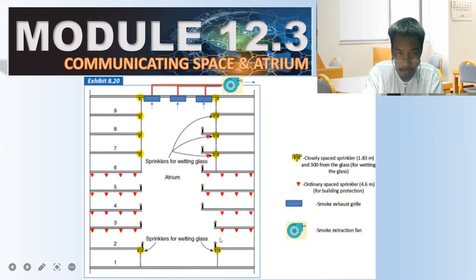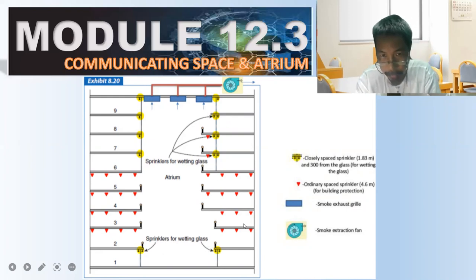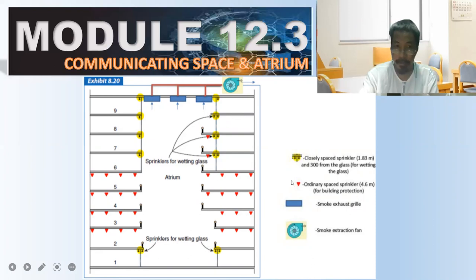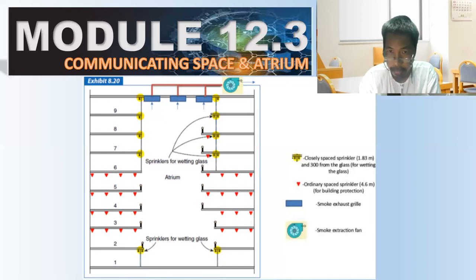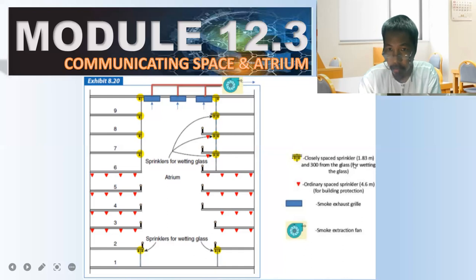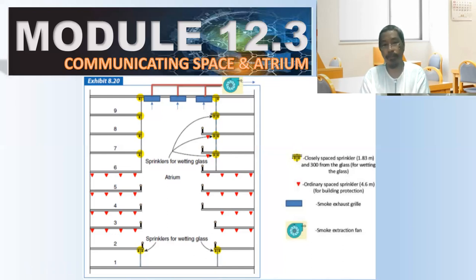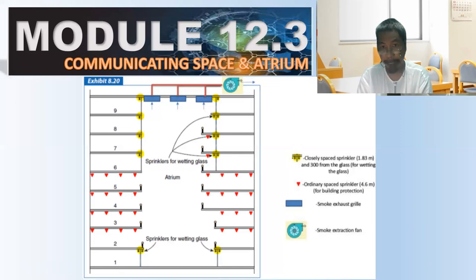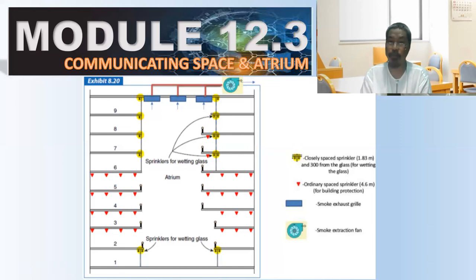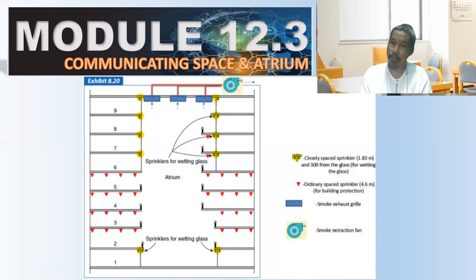This atrium is open from the second floor to the top floor. We have ordinary space sprinklers with a spacing of 4.6 meters — from one sprinkler to the next is 4.6 meters. The closely spaced sprinklers have a spacing of 1.83 meters. So ordinary spacing is 4.6 meters, and closely spaced is 1.83 meters — approximately 2.5 times closer.